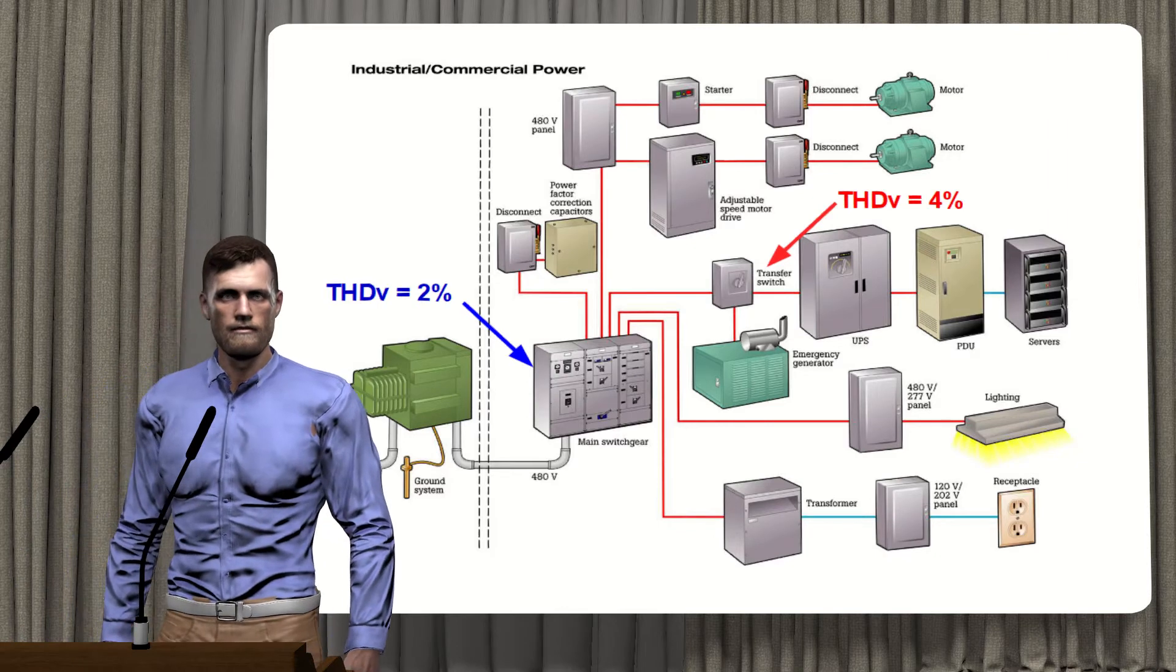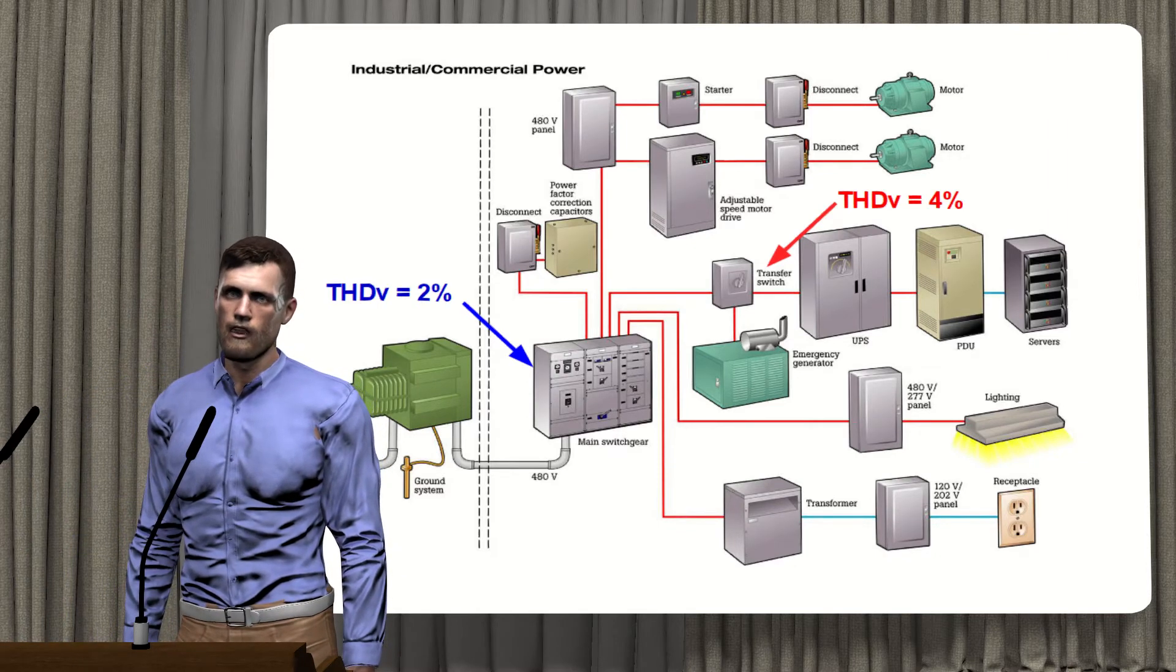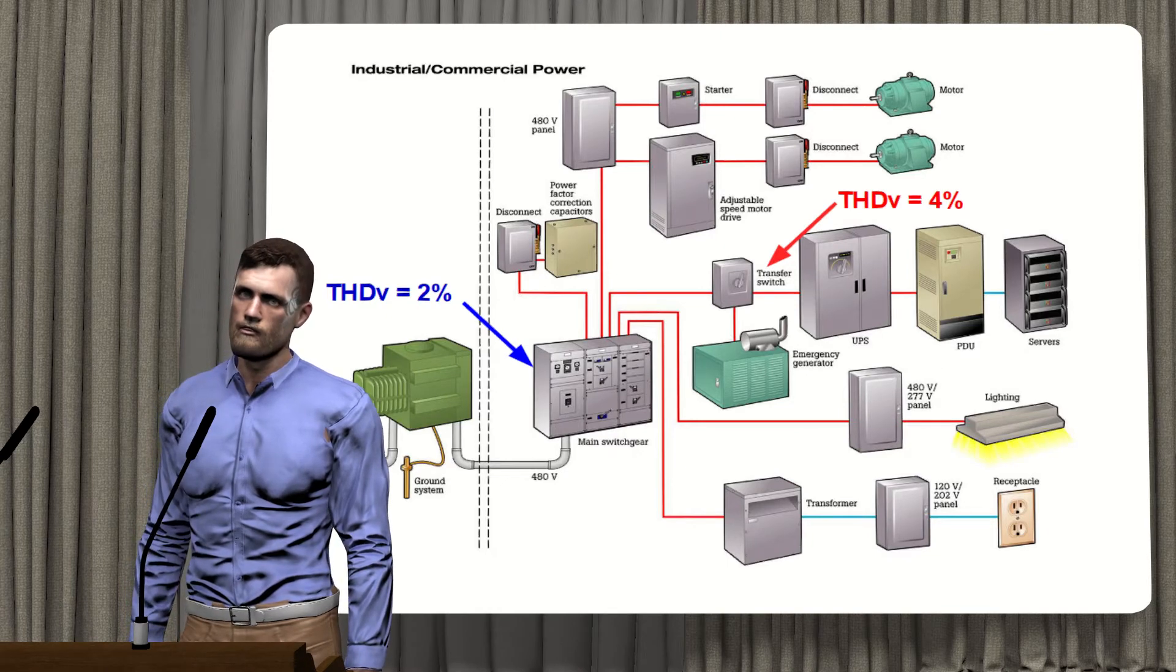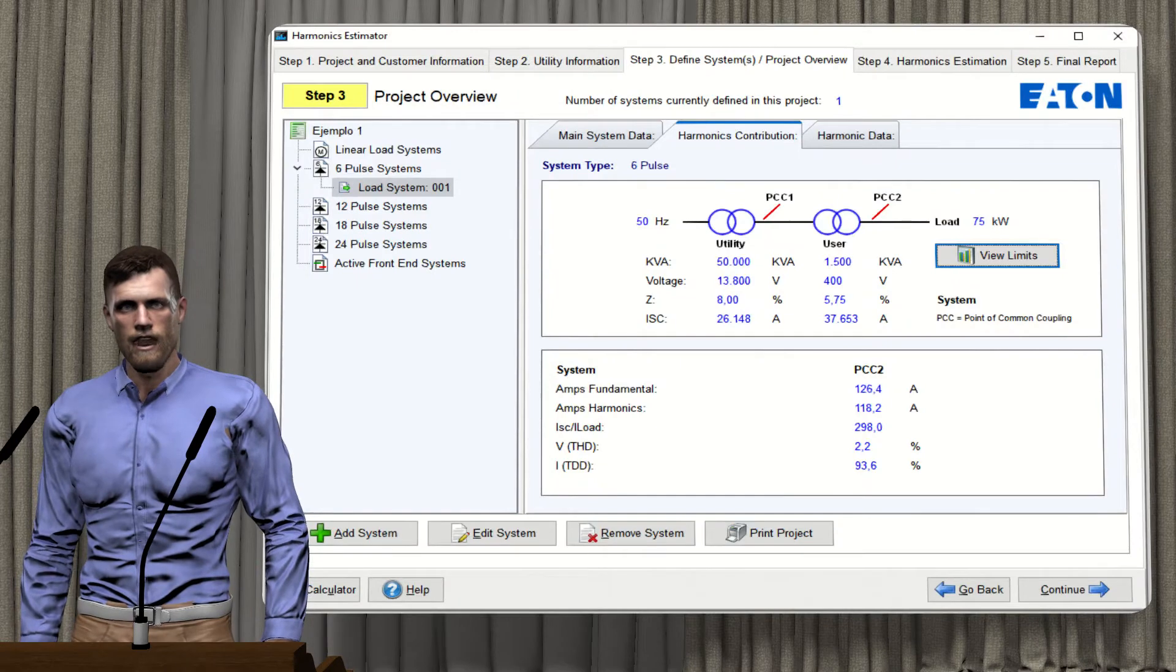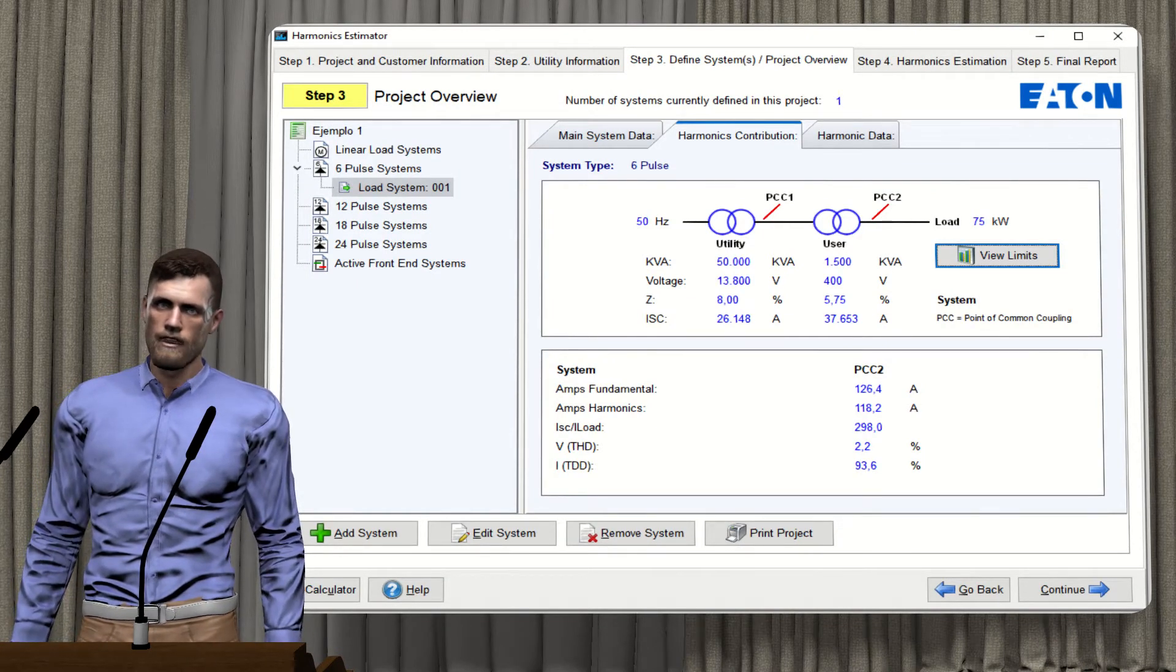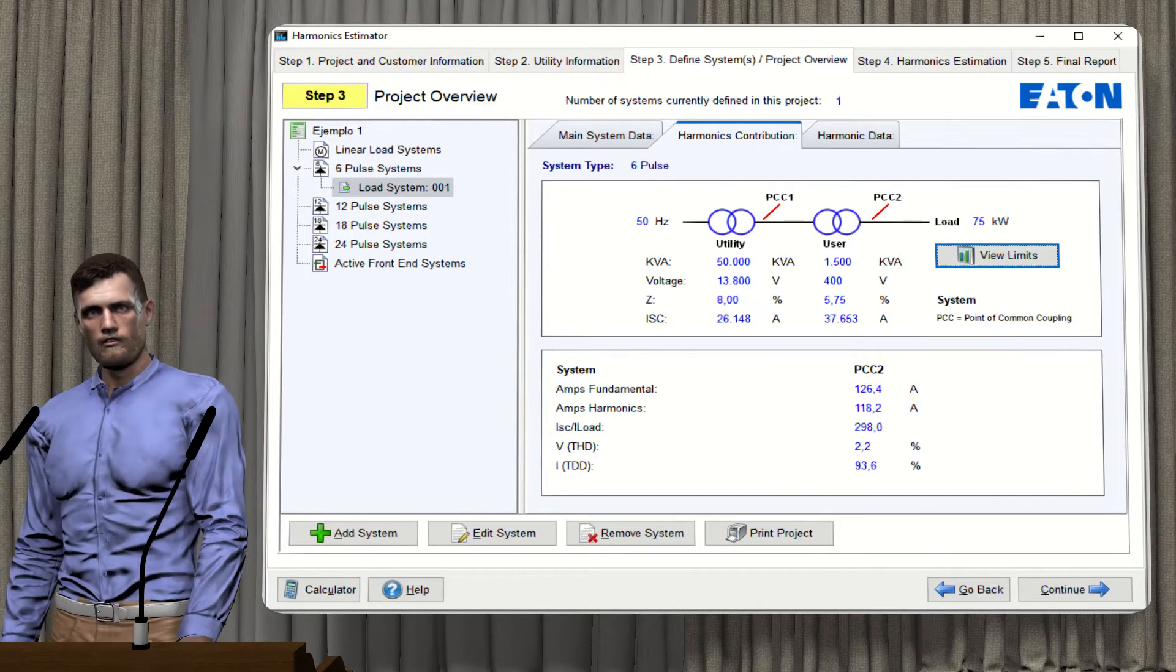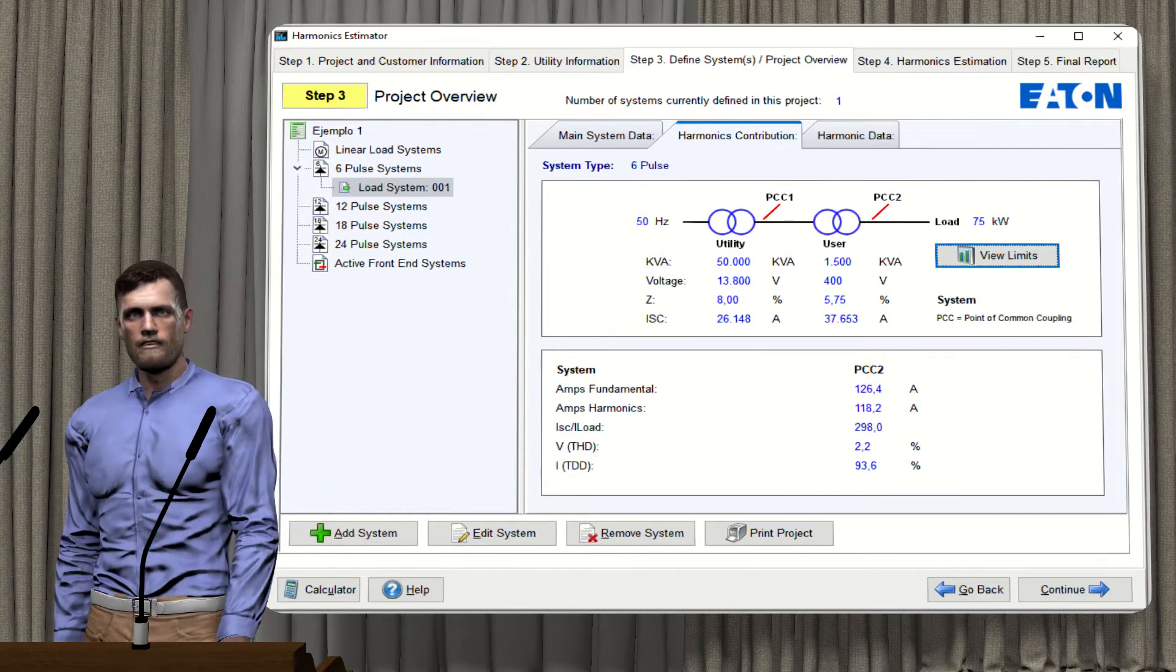For the current, the value provided by the THD can be very different depending on the type of loads that we consider. Here we can see the voltage and current THD associated with a variable speed drive with a 6-pulse input rectifier stage, provided by this harmonic calculation software. We would be talking about values around 2% for voltage and around 93% for current.